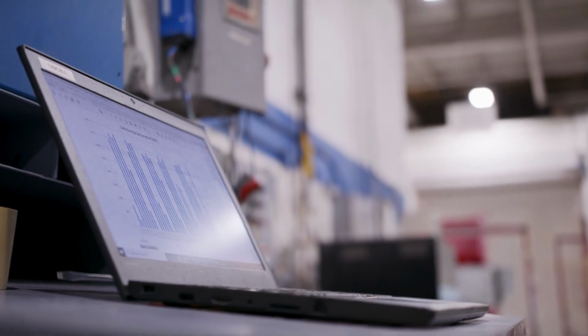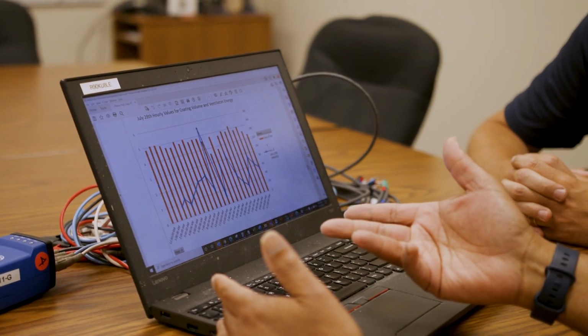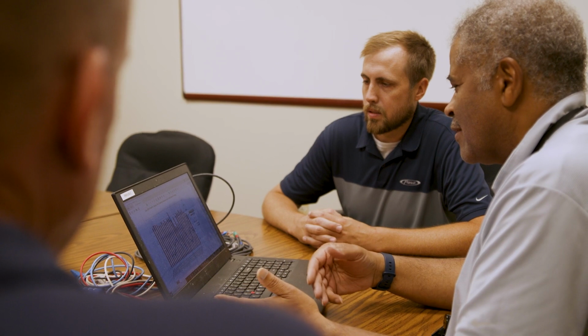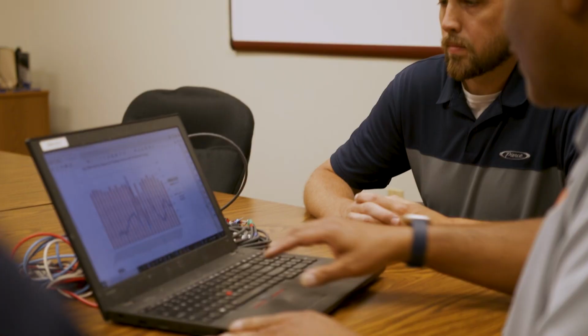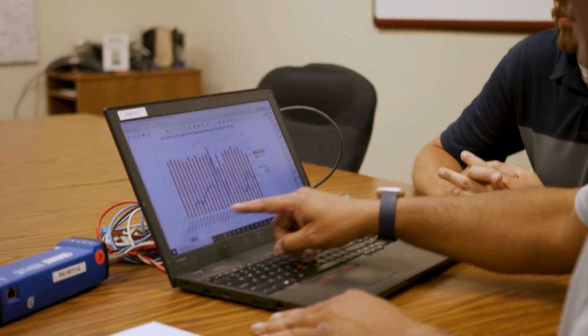What we learned from those meters was what the actual electrical consumption was. Before then, it was only an estimated and a calculated guess. What we were able to see was actual run times, what was actually being pulled, at what times during the day. It actually gave us a snapshot of what that booth was doing 24/7.